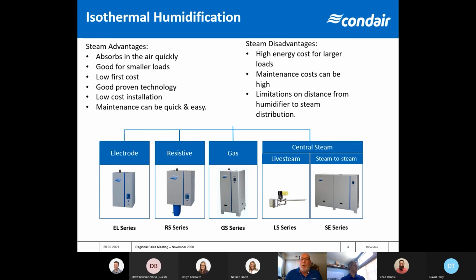The RS series, it's another electric humidifier, but it has resistive heating elements. So with these, we can use any kind of water we want. We can use potable, softened, RO, or DI water. And with the resistive units, we have the best controllability available from our steam humidifiers. We can do super tight tolerances. So both of these, the electrode and the resistive, these are great for what I call kind of small to medium-sized loads. As the loads get bigger, maybe start thinking about gas, where we can use natural gas or propane as the energy source to boil water.